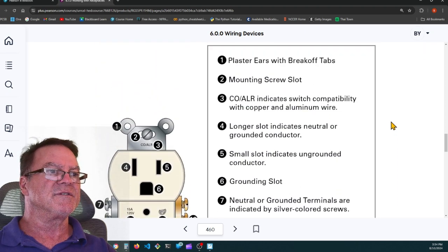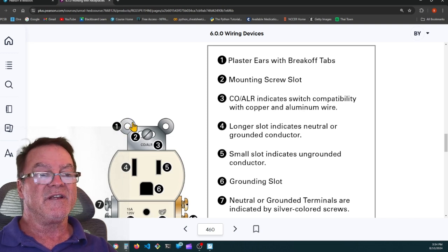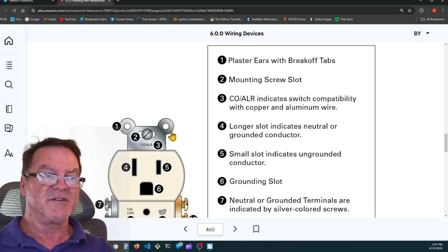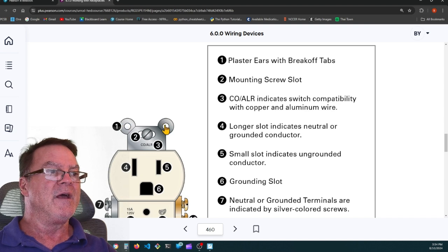Let's go over these. What does this say? It has plaster ears with break-off tabs. If you put these in a 4 square box with an industrial plate, then you need to break these ears off. Mounting screw slot is 3. COALR, that means it's good for copper or aluminum. COALR indicates switching capability with copper and aluminum wire. 4 is the longer slot. It indicates it's the neutral or grounded conductor.